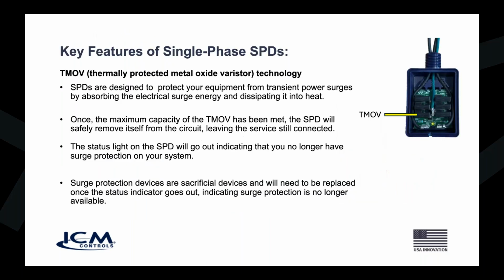So some of the key features of the single phase surge protected devices. The ICM products, and a lot of your products today, even other models in the field similar to the ICM product, are going to be using what they call thermally protected metal oxide varistor technology, TMOV technology. You're going to hear that word a lot if you're dealing with surge suppressors. And what that indicates is that these SPDs, or surge protective devices, these TMOVs, are the surge elements. Those are what's doing the protecting.